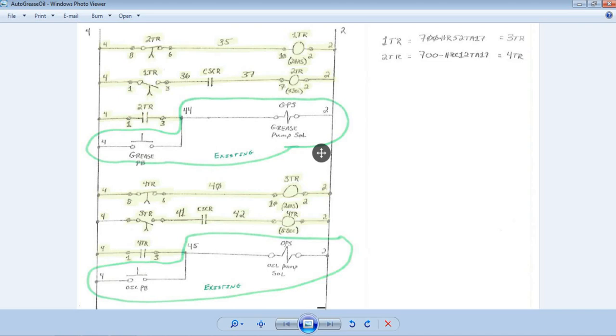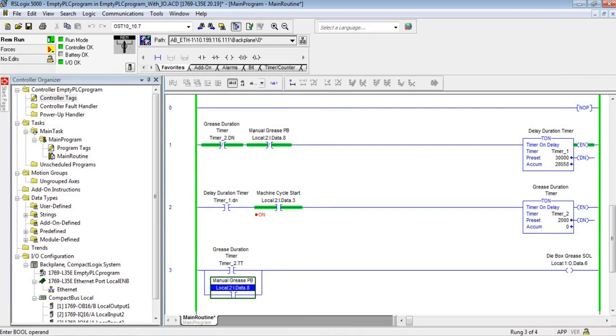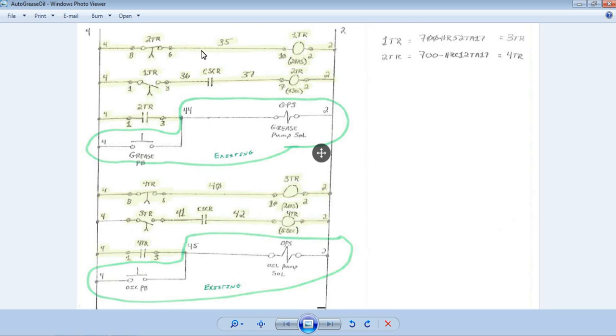Now notice that if I were to want to add that little feature that I did - just throwing this in the hardwire print - that becomes a lot of work. I've got to cut into wire 35, relabel some physical wire, either cut it and add a piece of equipment to the wire or run some long wires out to the operator panel. It's a lot messier than it is to just wire the inputs to a PLC and wire the outputs from the PLC. Whether you use terminal block to do that or directly wire to the PLC, it doesn't really matter. I personally like to go to terminal block because it's easier to modify things. It gets really crowded at a PLC a lot of times.